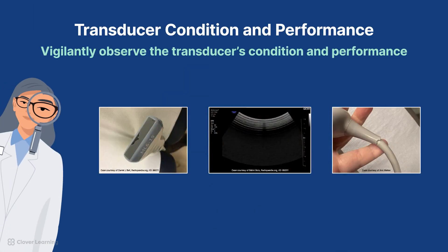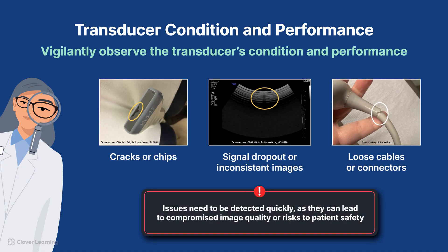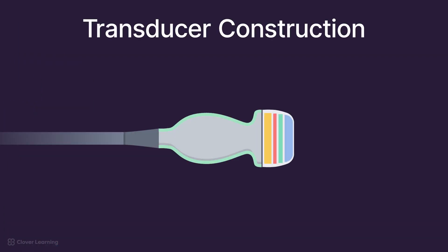Along with cleaning and storage, you should also be vigilant in observing the condition of the transducer and its performance. Cracks or chips in the protective housing, signal dropout or inconsistent images, and loose cables or connectors need to be detected quickly, as they can lead to compromised image quality or, worse, risks to patient safety.